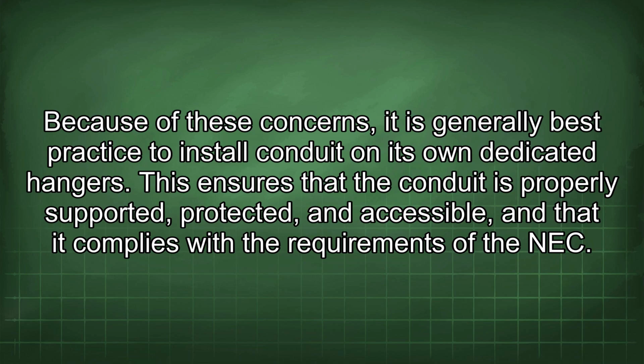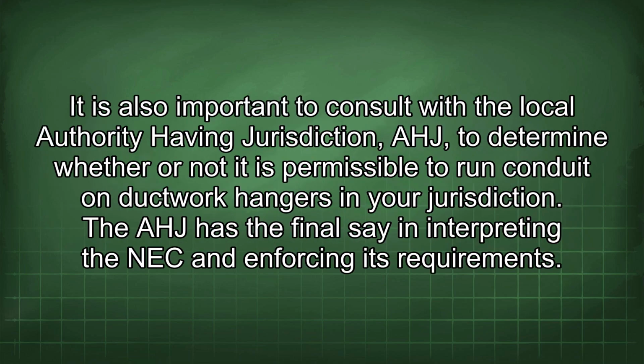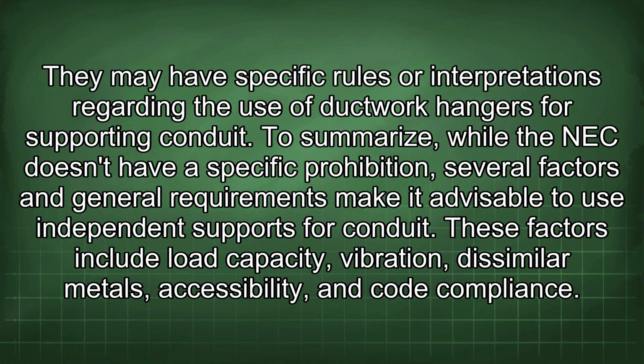Because of these concerns, it is generally best practice to install conduit on its own dedicated hangers. This ensures that the conduit is properly supported, protected, and accessible, and that it complies with the requirements of the NEC. It is also important to consult with the local authority having jurisdiction to determine whether or not it is permissible to run conduit on ductwork hangers in your jurisdiction. The AHJ has the final say in interpreting the NEC and enforcing its requirements. They may have specific rules or interpretations regarding the use of ductwork hangers for supporting conduit.